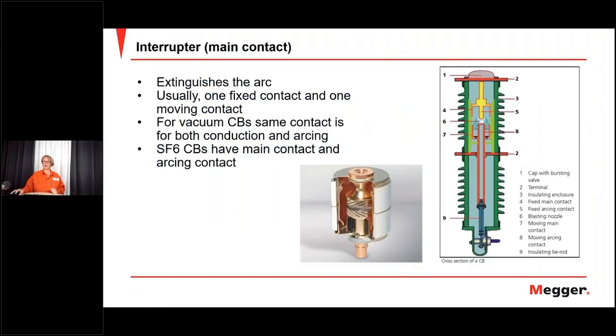Interrupters, yeah, here we have a part where we can see inside. You see the nozzle here, a little bit bluish, and the main contacts, upper and lower, and the arcing contact. So the difference here is the arcing contact: the SF6 circuit breaker, it really goes into position, while here, where we have a vacuum breaker, it's two plates that meet. So they are totally different in the way they behave and work.